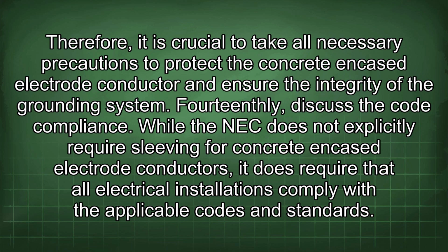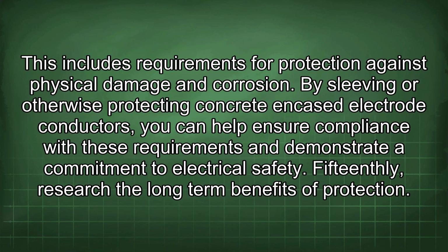14thly, discuss the code compliance. While the NEC does not explicitly require sleeving for concrete encased electrode conductors, it does require that all electrical installations comply with the applicable codes and standards. This includes requirements for protection against physical damage and corrosion. By sleeving or otherwise protecting concrete encased electrode conductors, you can help ensure compliance with these requirements and demonstrate a commitment to electrical safety.